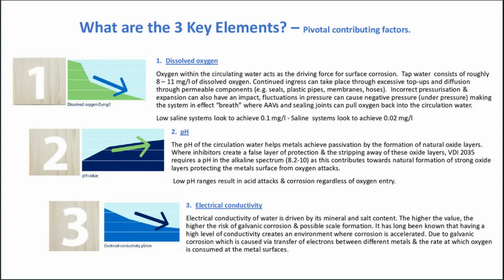Incorrect pressurization and expansion can also have an impact. Fluctuations in pressure can cause negative pressure, so that's an under pressure, making the system in effect breathe, where air vents and sealing joints can pull oxygen back into the circulation water. So if we look at low saline systems, we're looking to achieve 0.1 milligram per litre, and saline systems look to achieve 0.02 milligrams per litre.